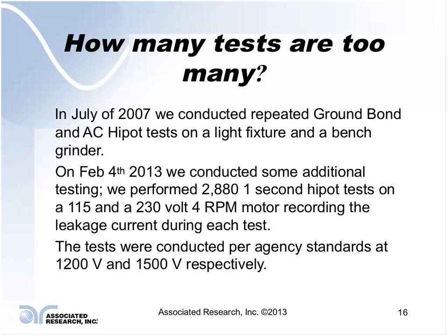We've done some tests here on various products throughout the years, and here's some examples. Back in 2007, when we first put this first webinar together, is repeated Hipot testing destructive? We took a couple different types of products and we did some multiple tests on them. We hooked them up. I had a bench grinder that I purchased to go through and actually do demonstrations with.